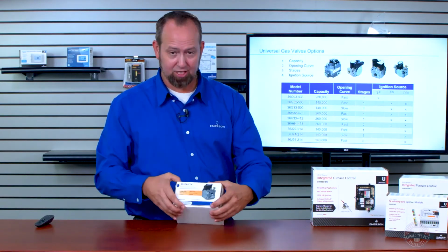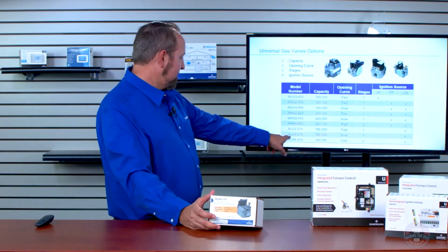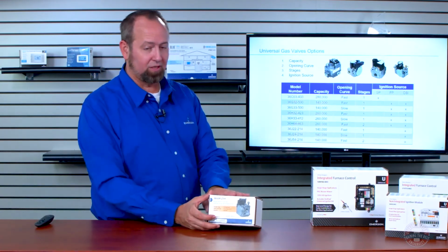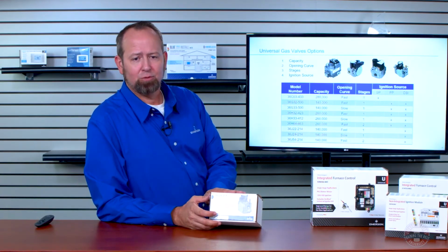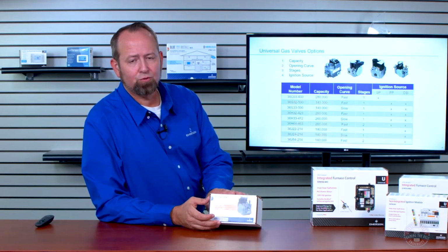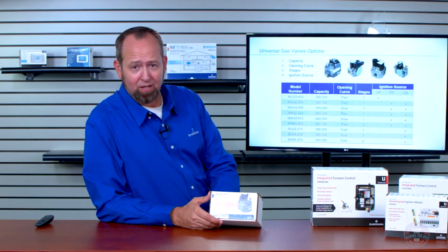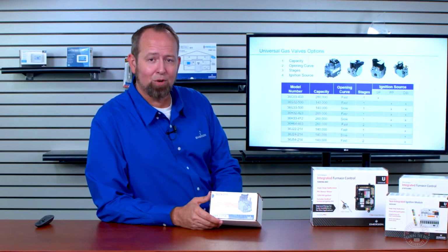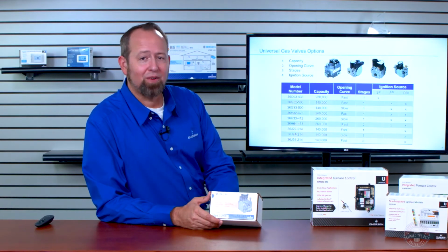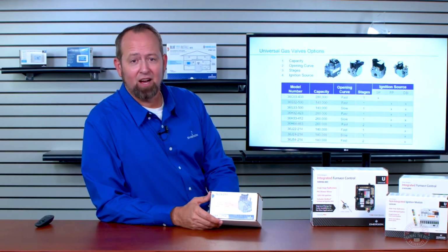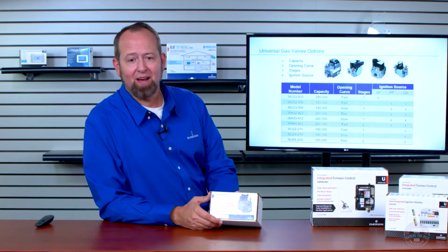And this 36J is the 24214. It is the slow open version that we have here. Why slow open versus fast opening? Well, those really are determined by the furnace manufacturer and how they design the burners.